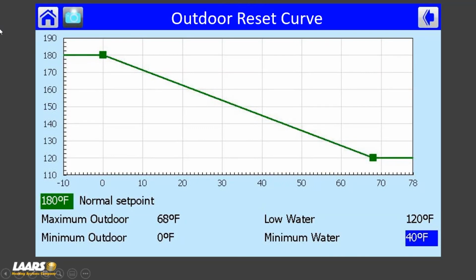So in the example I used, 0 degrees will hit our high temperature. Also, in this example, it's 68 degrees. So if it's 68 degrees out, do we really need 180 degrees to heat that space? Absolutely not. And I chose a value of 120. And you can customize this. You know, Massachusetts may be 10 degrees above 0 is your design day. Well, at 10 degrees, maybe you want 180. Minneapolis might be -5 degrees. You want 180. But also look at that dwelling. Is it a new home with blown-in insulation, brand new windows, or is it a 1953 home with poor insulation and drafty windows? And if that's the case in the Massachusetts market that I said at 10 degrees will achieve 180, no, maybe at 20 or 25 degrees of outdoor air, I want to achieve 180. So you customize these. Okay?